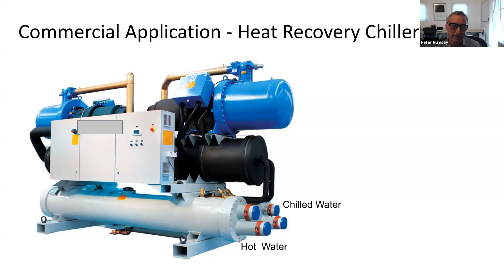So there's lots of buildings that simultaneously need heating and cooling, and we can do that with a heat recovery chiller. So that makes it very efficient. Stanford recently built a brand new central plant, and this is in California, where they have a very large scale heat recovery system. And the tanks that you see there are million-gallon tanks that store hot water or chilled water.